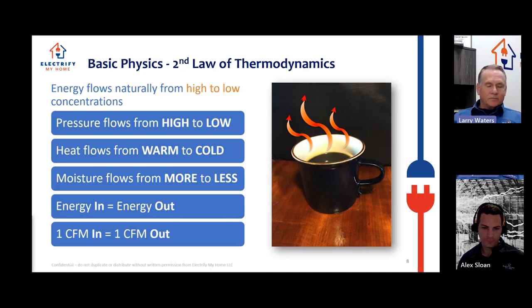We want to remember pressure differentials. Pressure is always going to move from high to low. Heat is always going to move from warm to cold. Moisture is always going to flow from the big puddle to the little puddle. Energy in is going to equal energy out. And if you have an air leak, if it leaks out 1 CFM on that side of the house, that 1 CFM is coming in from the other side of the house. So these are the important ones that we need to know as part of our design and understanding of how these systems work.